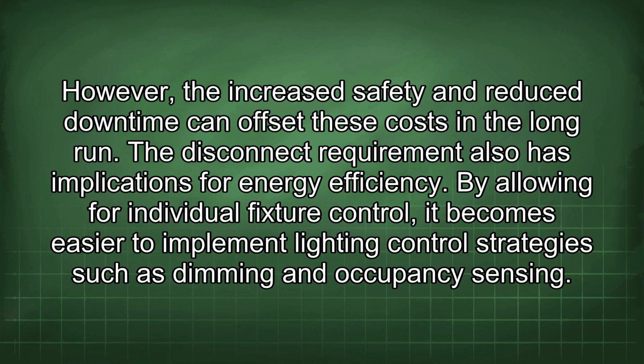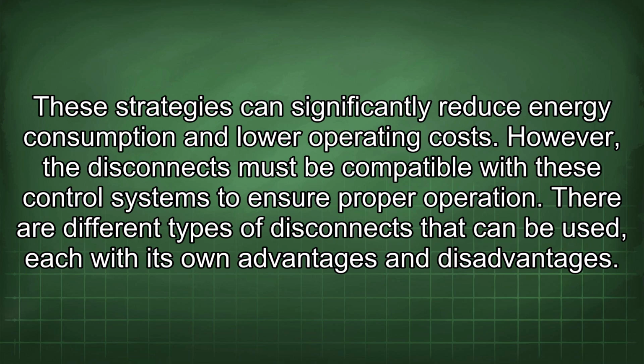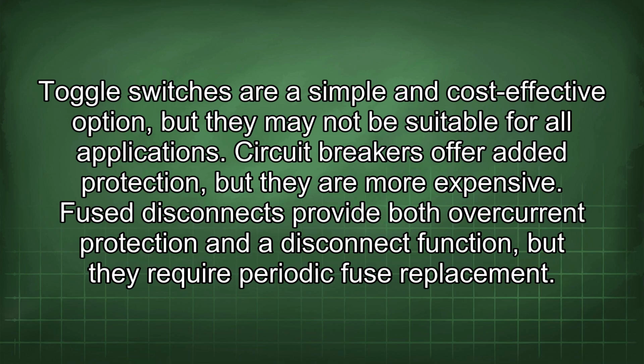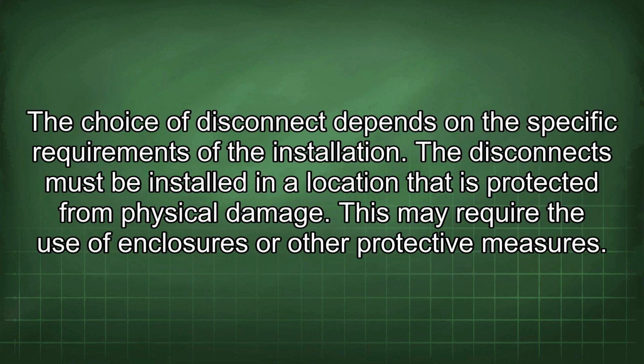The disconnect requirement also has implications for energy efficiency. By allowing for individual fixture control, it becomes easier to implement lighting control strategies such as dimming and occupancy sensing. These strategies can significantly reduce energy consumption and lower operating costs. However, the disconnects must be compatible with these control systems to ensure proper operation. There are different types of disconnects that can be used, each with its own advantages and disadvantages. Toggle switches are a simple and cost-effective option, but they may not be suitable for all applications. Circuit breakers offer added protection, but they are more expensive. Fused disconnects provide both overcurrent protection and a disconnect function, but they require periodic fuse replacement. The choice of disconnect depends on the specific requirements of the installation.